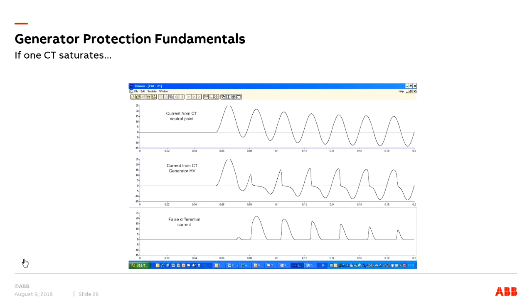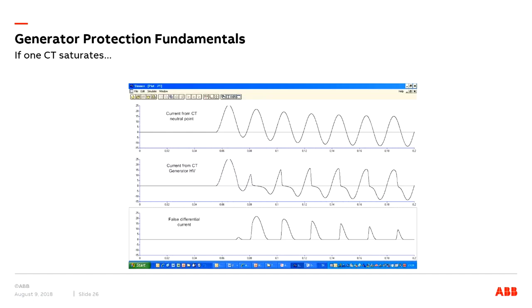So here's a look at a picture for CT saturation. If the CT on one side of the generator saturates while the CT on the other side is unaffected, there will be a significant false differential current. As you can see here, this is the current from the CT neutral point and the current from the generator terminal side, and this CT is going through saturation, which will cause this false differential current to be seen by the relay. For short intervals, there is a risk that the differential current enters the trip area, so we need to handle the situation.